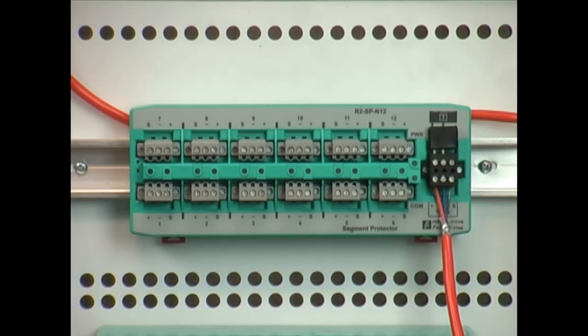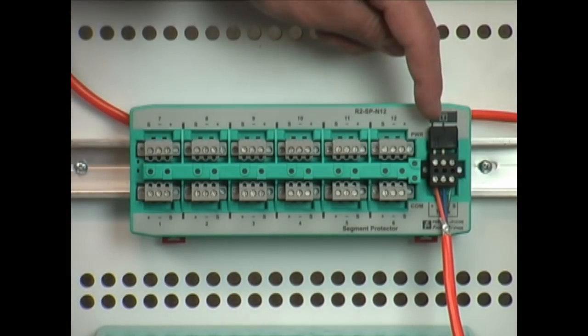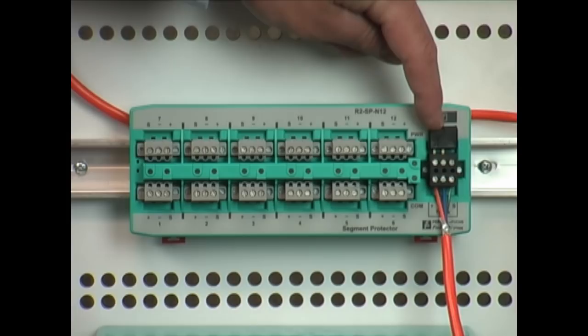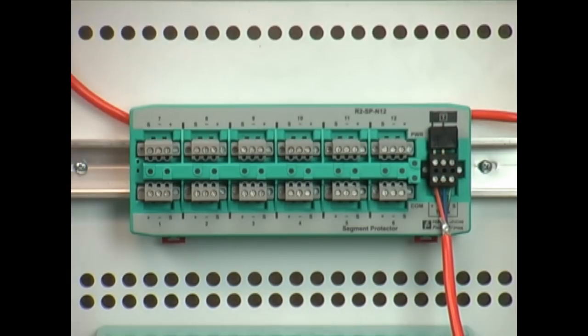Additionally built into the segment protector is the second terminator that you need for your Foundation Fieldbus segment. So again it's already included with the segment protector and makes it easier to ensure that you have two per segment.